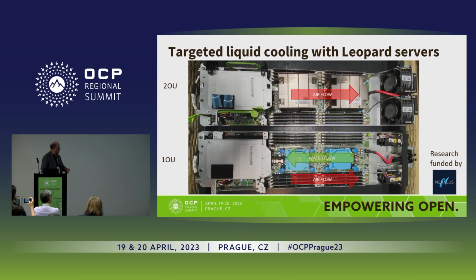So we took these repurposed servers and we said, okay, let's throw away those very cheap heat sinks with a couple of heat pipes in them, brazed aluminium, and let's put on some water blocks or cold plates, and we're using these cold plates supplied by Nexalus. And the interesting thing is that the airflow on the server goes that way, but when you're only concentrating on the microprocessors, you still have to cool other parts of the IT. So you can see there's an airflow and a water flow in opposite directions in the setup.